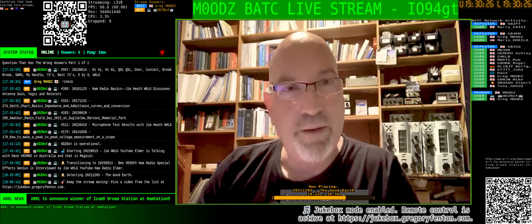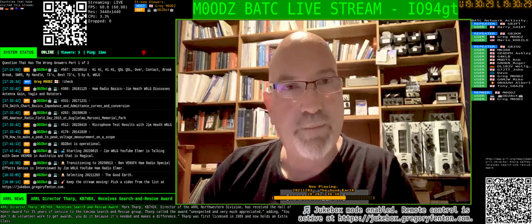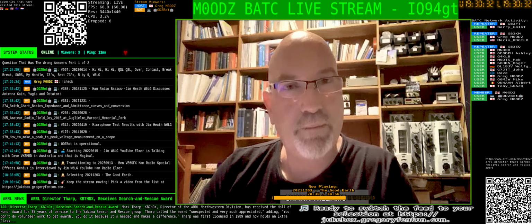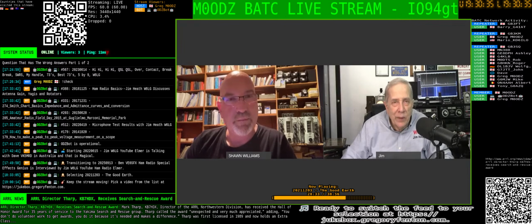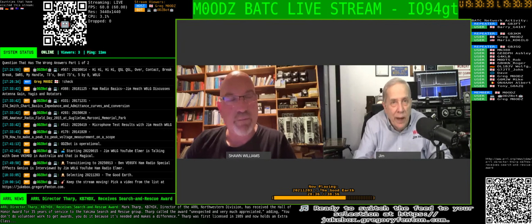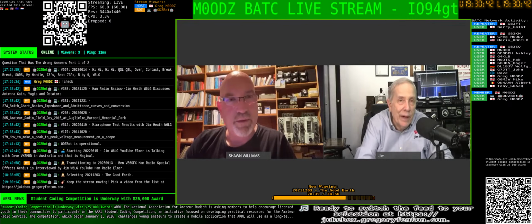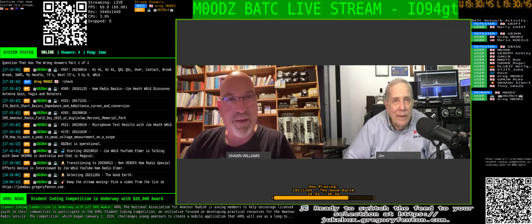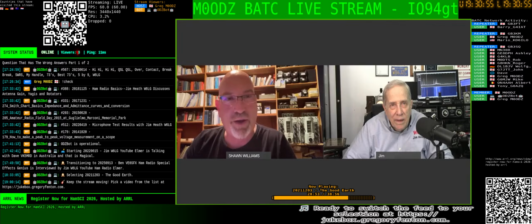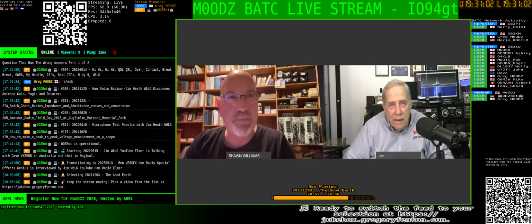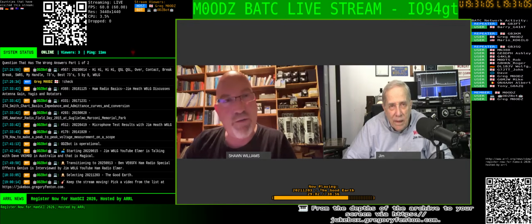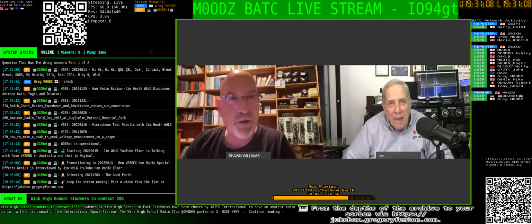You're right. I've seen it several times where the gas company, natural gas, comes out, takes a measurement where they're connecting natural gas, and drives another rod because they're not happy with the resistance, in particular of the ground, which is a whole other issue. That's also in the NEC, and this is what's called an auxiliary electrode. There are a few ways you can get around the code for auxiliary electrodes. One of them is a provision, 250.54. It's really a silly regulation, but it exists.